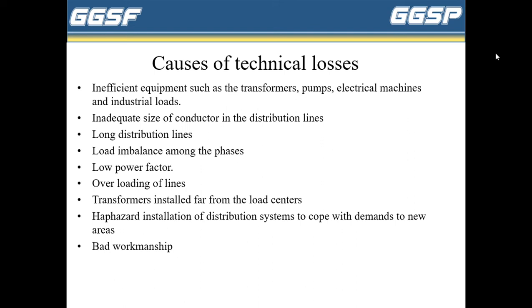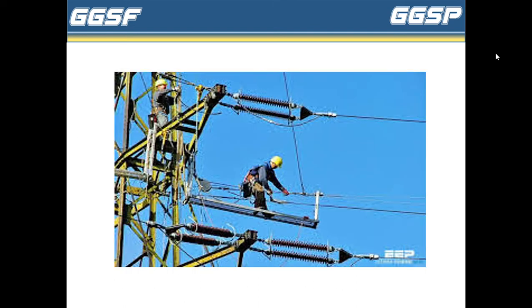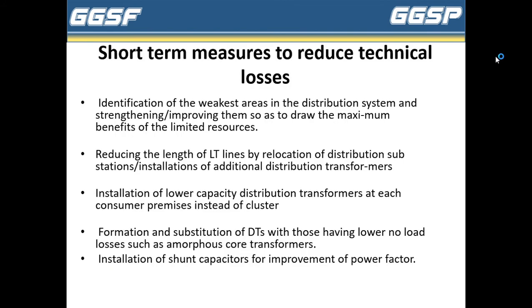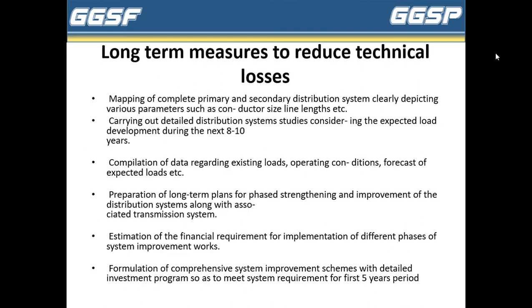Let's discuss measures to reduce technical losses. Short-term measures include identification of the weakest areas of the distribution system, reducing the length of LT lines by relocation of distribution substations, installation of lower capacity distribution transformers, formation and substitution of DTs with those having lower no-load losses such as amorphous core transformers, and installation of shunt capacitors for improvement of power factor.